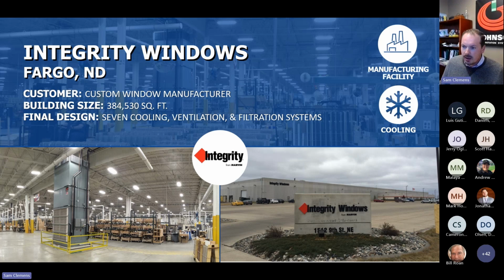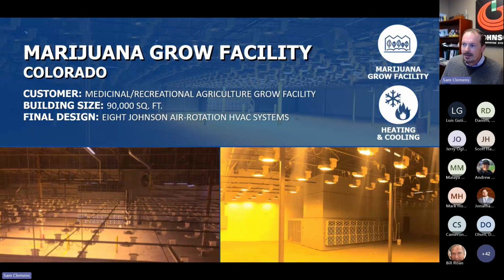Local to the Denver area, this is an interesting one. It's not unlike what we see in many industrial applications, and it speaks to many value propositions with the air-rotation design. Originally here, they were going to put big pieces of unitary gear on this 90,000 square foot building to satisfy a 1,200 ton load. Instead, they got rid of all the ductwork, plunked in 8 air-rotation units strategically, and we were able to guarantee the temperature and humidity uniformity throughout.